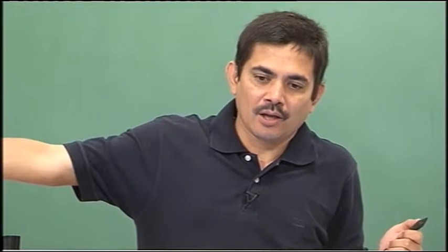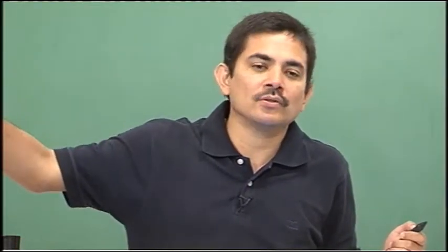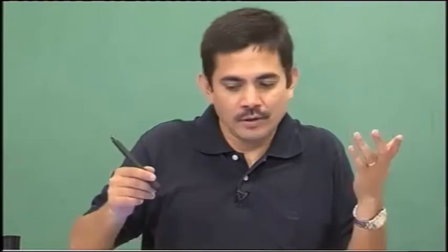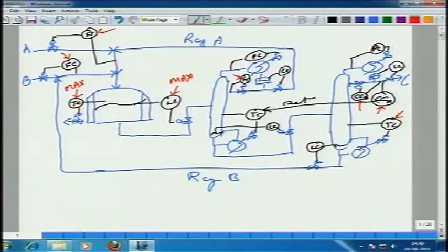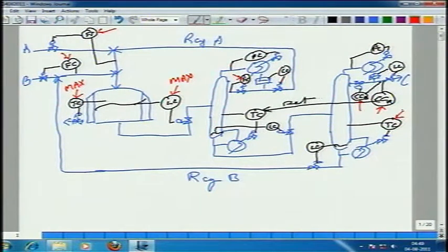Okay. But from a practical standpoint, there are always side reactions, and because there are side reactions, there is a limit as to how much C you can allow to leak out. See what I am saying? So, you have a way of setting the temperature controller set point 2. In a similar way, the reflux set point also gets set in the first column, the recycle column. You can't allow too much A to get recycled, or too much, what should I say, what is the impurity here?